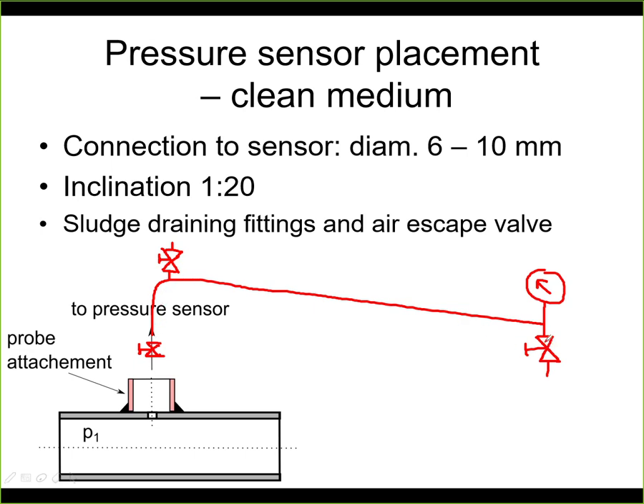And here on this position, the lowest position, you should have a valve that allows you to drain any impurities. So if you need to remove these impurities, they will accumulate at the lowest position because they are the heaviest. They will accumulate here, and from time to time you will open this valve, you will drain those impurities, and you will clean the system like this. So now those rules apply for clean mediums.